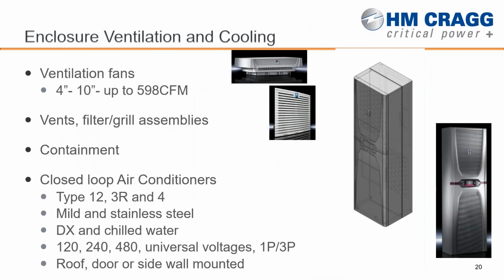So a little bit more on ventilation and cooling then. Ventilation fans, there's a variety of different sizes that you can select based on the airflow required to get any of the dissipated heat inside out. We have one ventilation fan up to almost 600 CFM. We can use multiple fans on the enclosure. We can add vents and filter grill assemblies if we're just doing a type 12 enclosure. We can add specific containment.